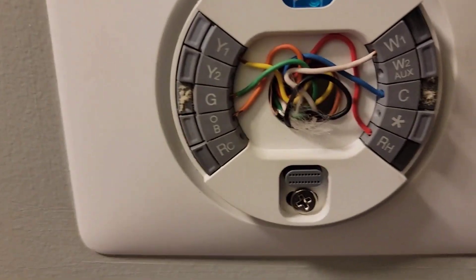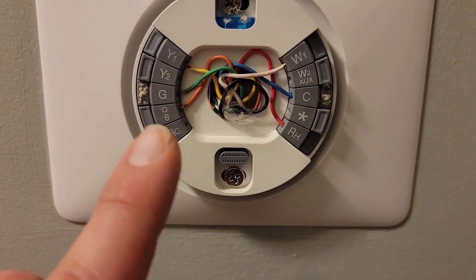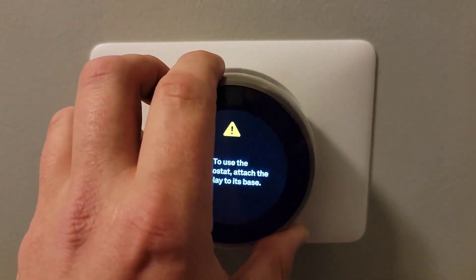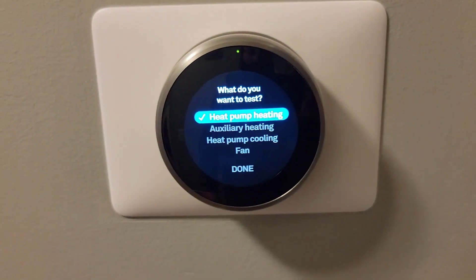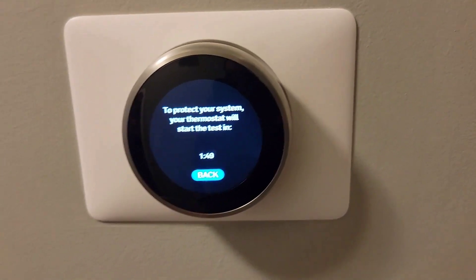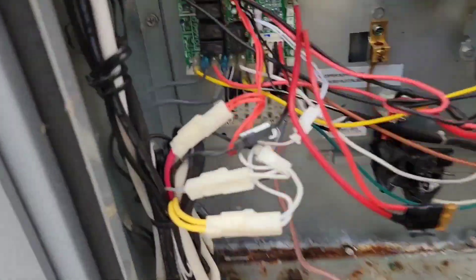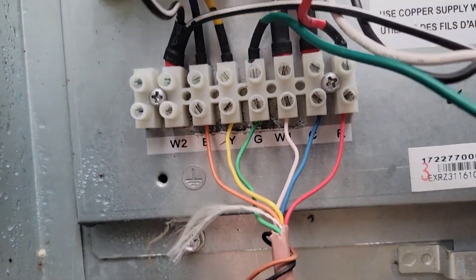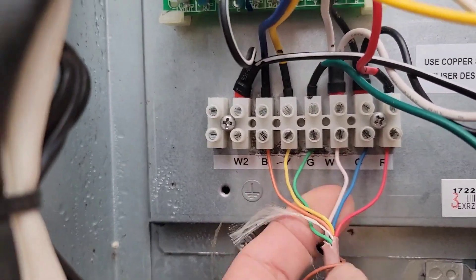See that orange wire going to the O/B terminal? Let me show you that. Let me reset this first. Let's go outside. Here's the package heat pump and here are the thermostat wires. You can see that orange wire is going to the B-terminal.